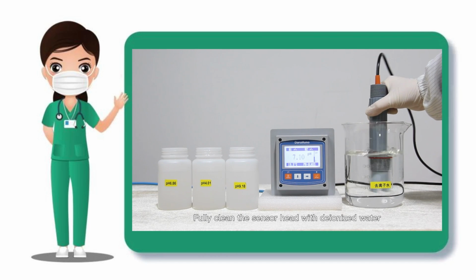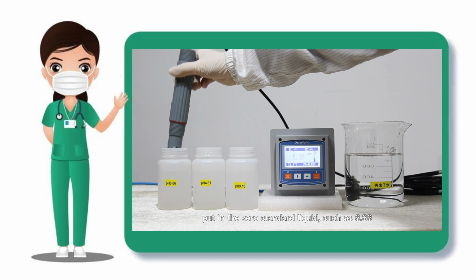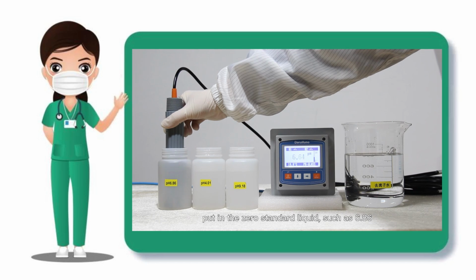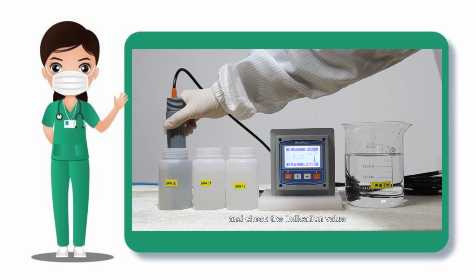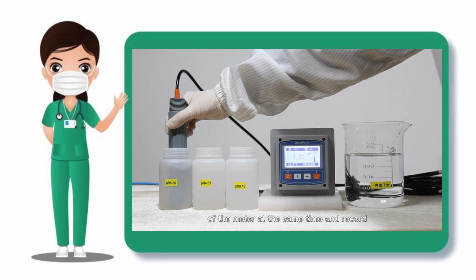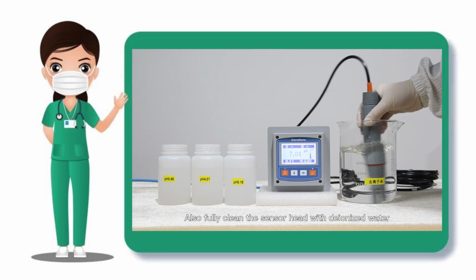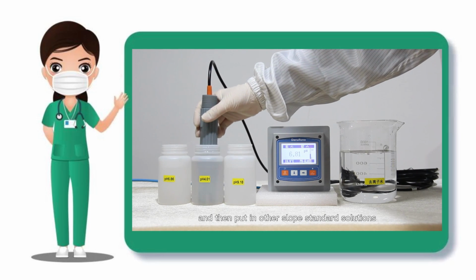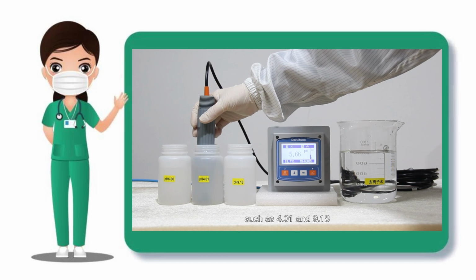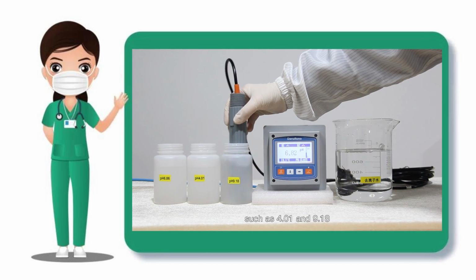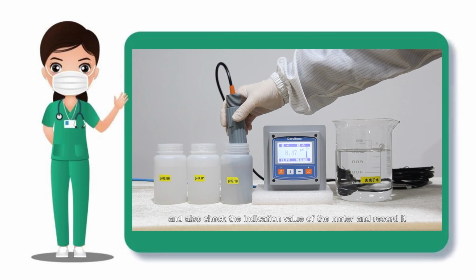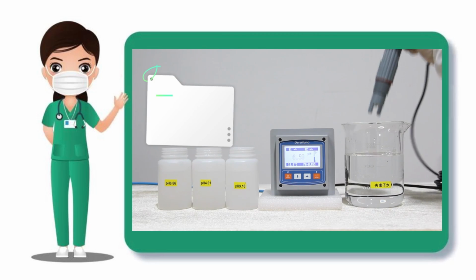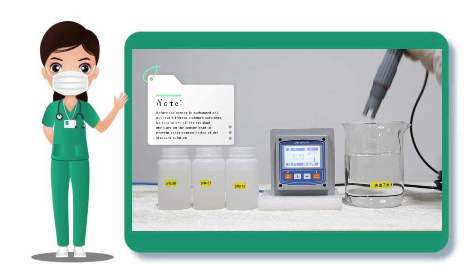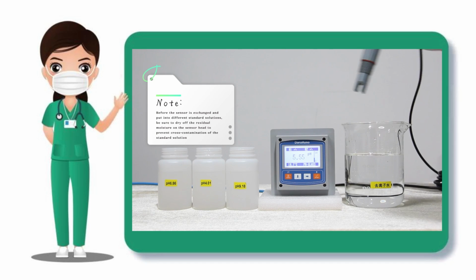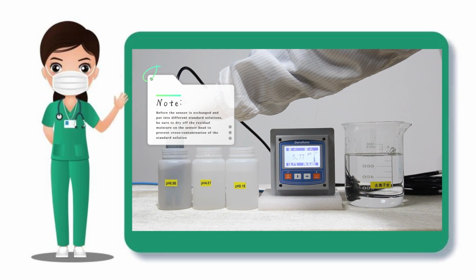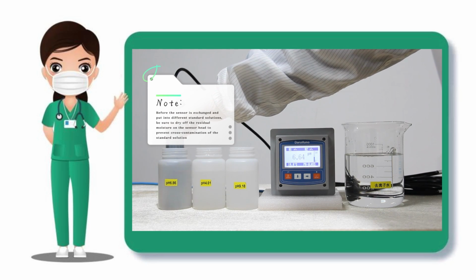Fully clean the sensor head with deionized water. Put in the 0 standard liquid, such as 6.86, and check the indication value of the meter at the same time and record. Also fully clean the sensor head with deionized water, and then put in other slope standard solutions, such as 4.01 and 9.18, and also check the indication value of the meter and record it. Note, before the sensor is exchanged and put into different standard solutions, be sure to dry off the residual moisture on the sensor head to prevent cross-contamination of the standard solution.